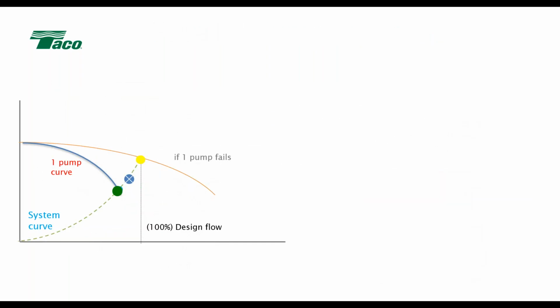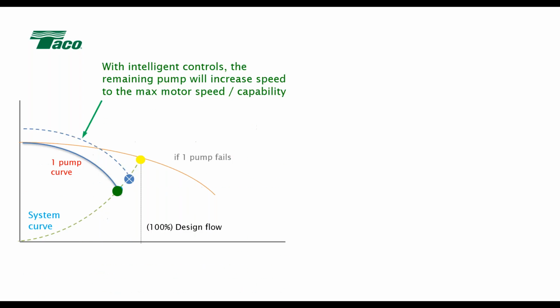So where does this redundancy come into the picture? When you have intelligent controls on the pumps, if one pump fails, the remaining pump will increase speed to the max motor speed and motor capability. We allow that pump to run out to where it hits the system curve at that max speed, which, if I size two pumps at 50% each, is generally about 70 to 75, maybe 80%, depending on the exact pump, of the design flow.